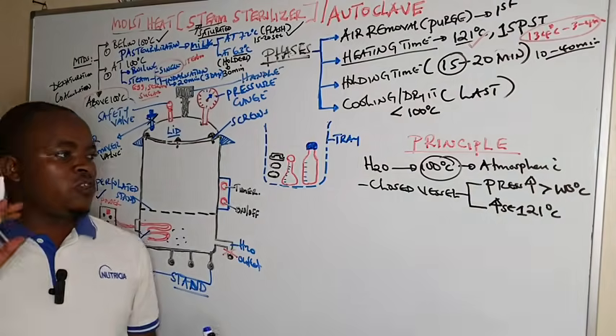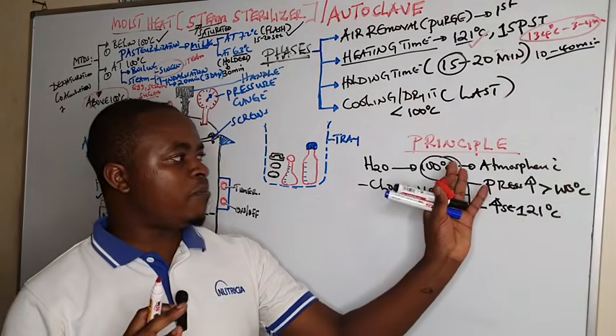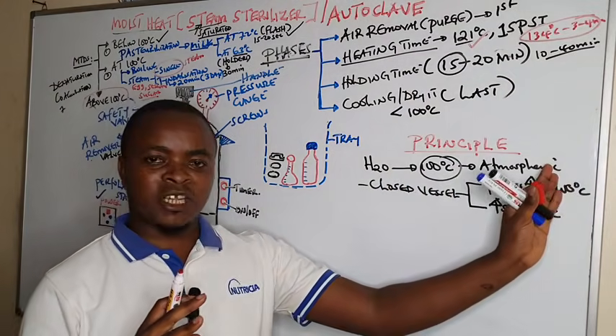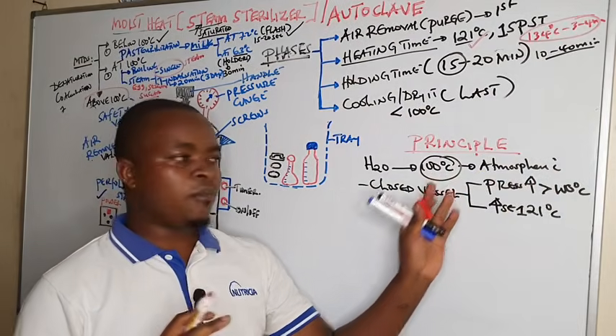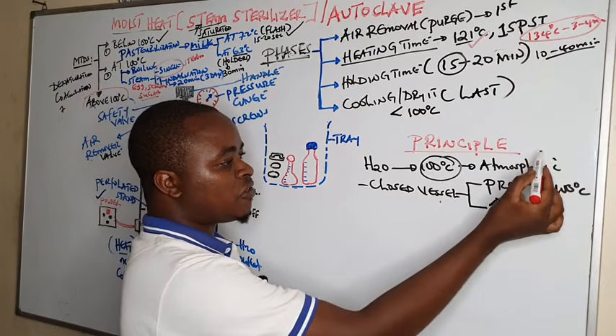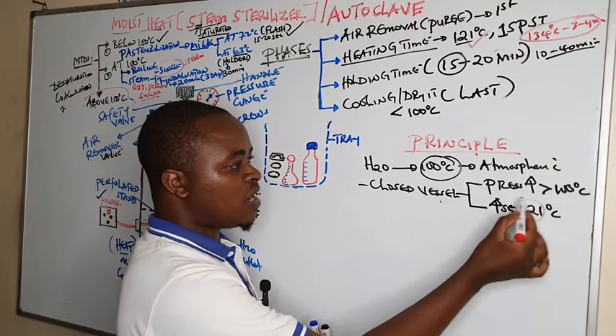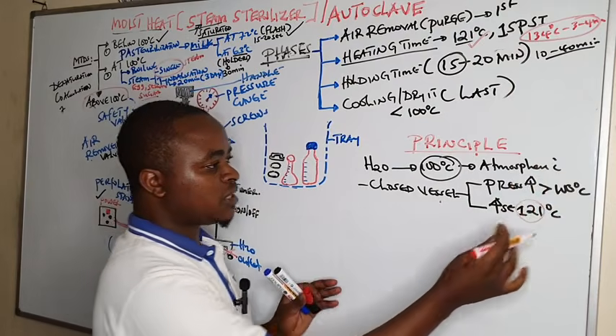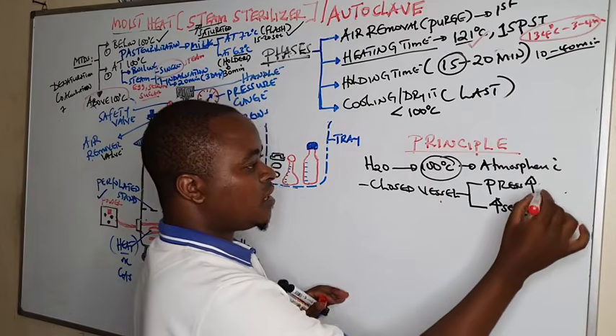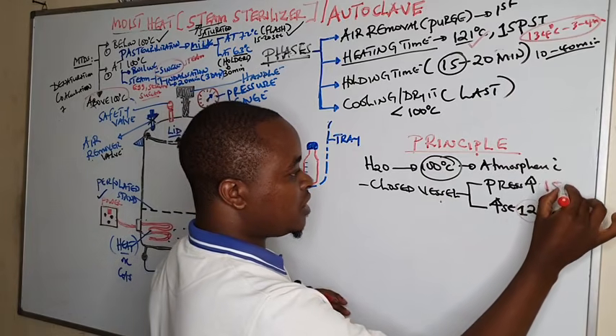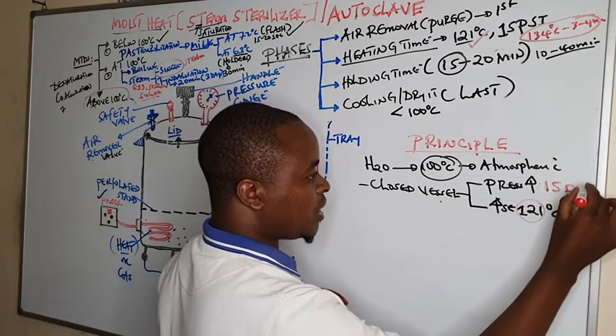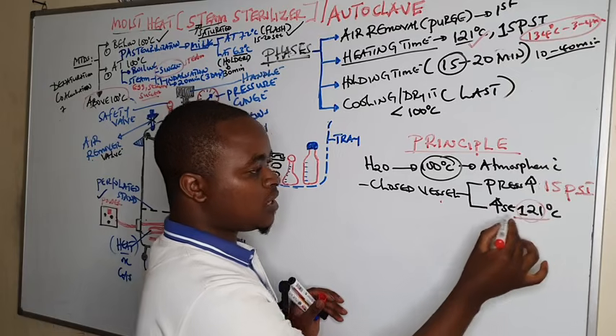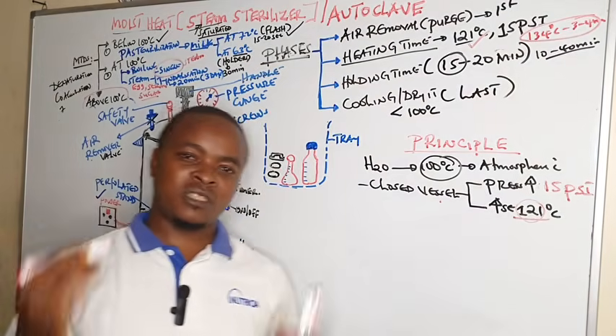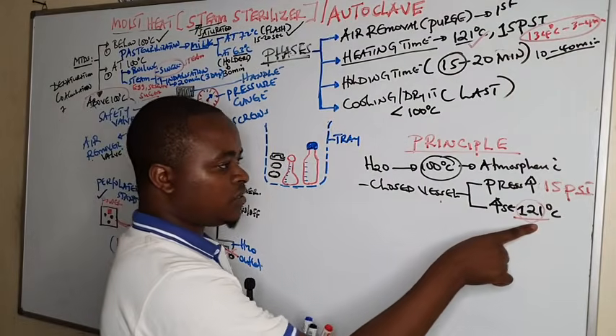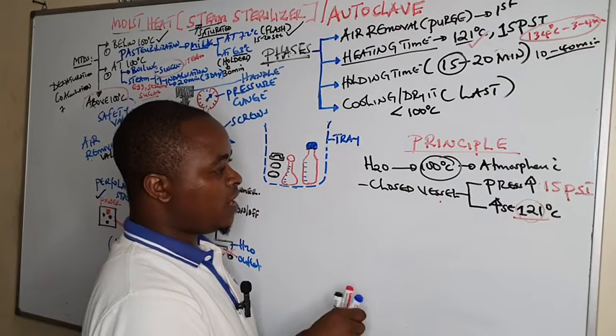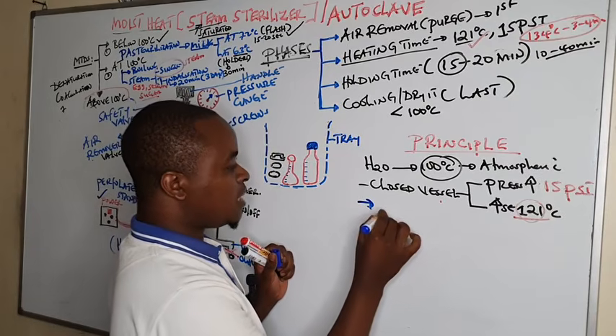So when you are boiling water in an open system, whereby the pressure is equal to the atmospheric pressure, water boils at 100. But in a closed vessel, when the pressure increases, that is when we increase it to 15 pounds per square inch, the temperature also increases above 100, that is 121. And this increase in the temperature is good enough to cause complete sterilization.